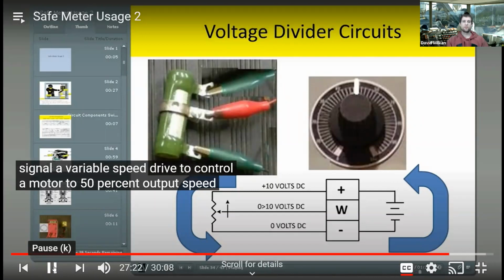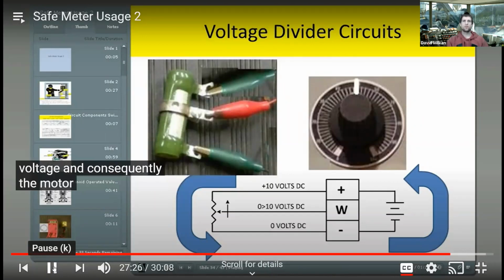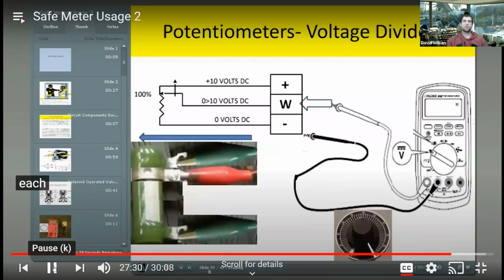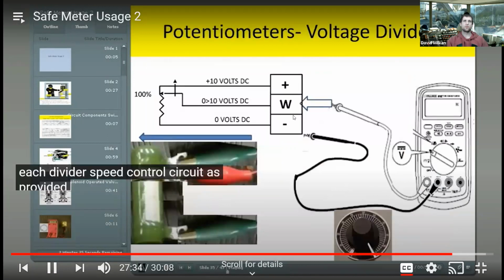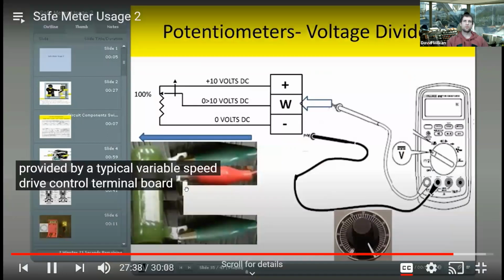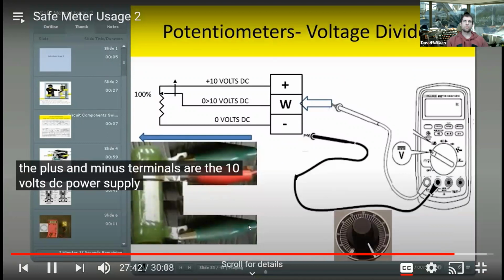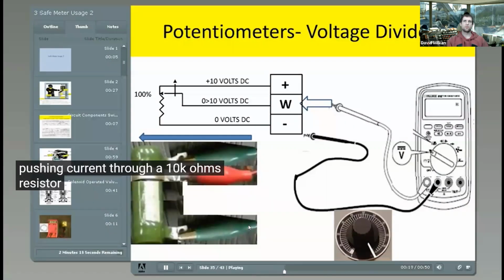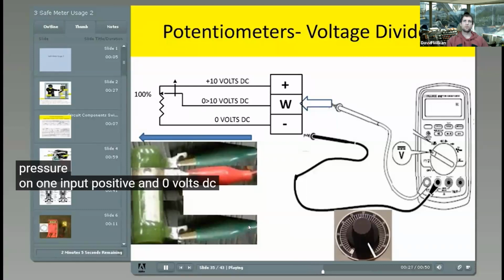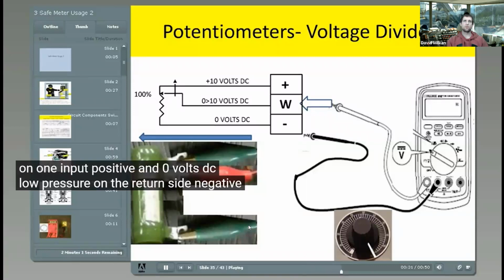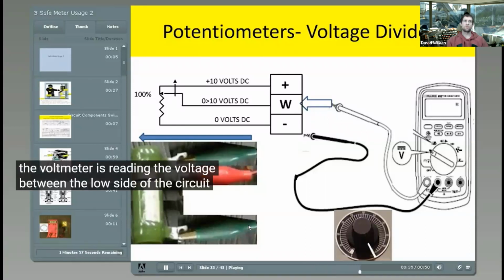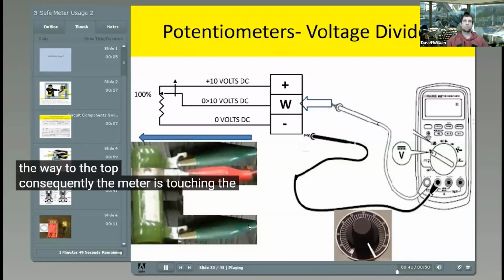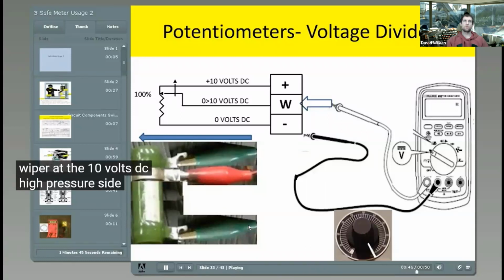To 50% output speed. Rotating the shaft would vary the voltage and consequently the motor speed. Divider speed control circuit, as provided by a typical variable speed drive control terminal board. The plus and minus terminals are the 10 volts DC power supply pushing current through a 10K ohms resistor. The resistor requires 10 volts DC, high pressure, on one input, positive, and 0 volts DC, low pressure, on the return side, negative. The voltmeter is reading the voltage between the low side of the circuit and wiper, W. The wiper is adjusted all the way to the top. Consequently, the meter is touching the wiper at the 10 volts DC, high pressure, side of the component and is reading 10 volts DC.